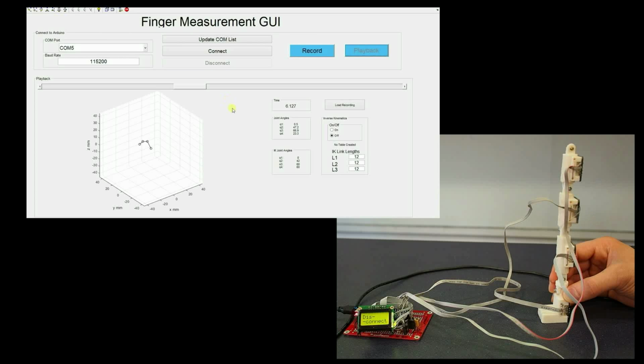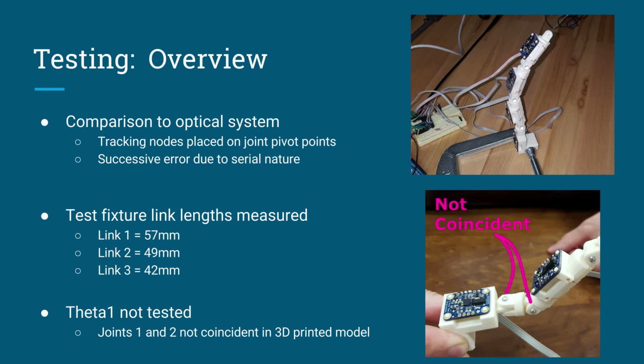There we go. Using the vision tracking system in the AIM lab, we were able to verify that our sensors are fairly accurate. Tracking nodes were placed on each of the pivoting joints of the test fixture. The XYZ location of these nodes should be directly related to the positions determined in the forward kinematics model. It was predicted that because the device is essentially a series of links, the error would compound over the length of the device.